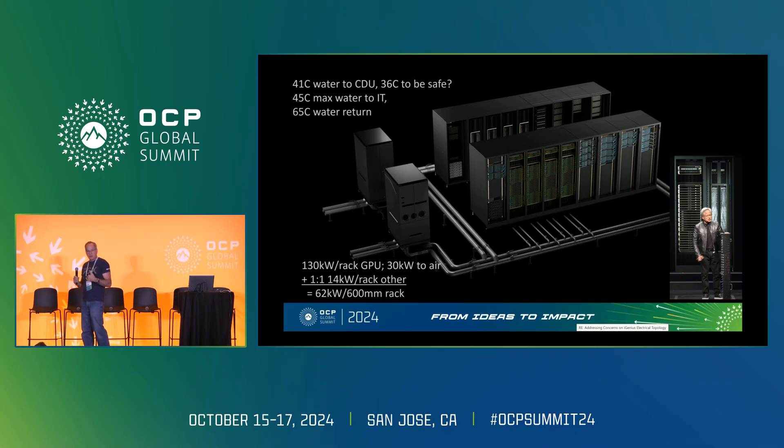What are the key requirements? You could put it in an air-cooled data center — you see a preponderance of sidecars doing liquid-to-air cooling. But we really think the answer is that data centers of the future need water. They don't need 18°C or 22°C water. Our chips run at a T-case of 85–90°C, which means we only need 45°C water. Most good CDUs have a 4°C approach, so 41°C is dry-cooler water everywhere in the world. That means no evaporative cooling towers, no blow-down and make-up water concerns, and no sizing for compressors. That 25% of data center power that was compressors — now you can put more IT in the kit.